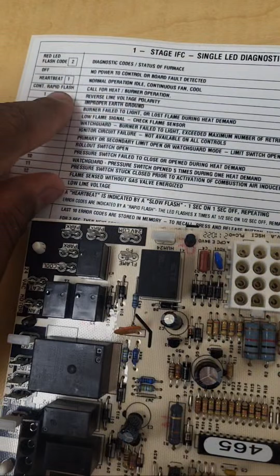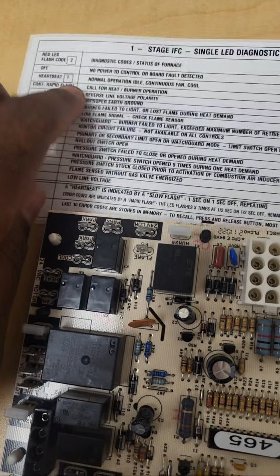Remember I was telling you a while ago, one thing I like about these Ducane furnaces is if a customer had an intermittent issue - meaning the customer stated the heat wasn't working last night, and then you get there and it works - all you have to do is look at the LED light to make sure it's blinking normal operation. It says here: continuous rapid flash means call for heat, burner operation, and one heartbeat means normal operation.